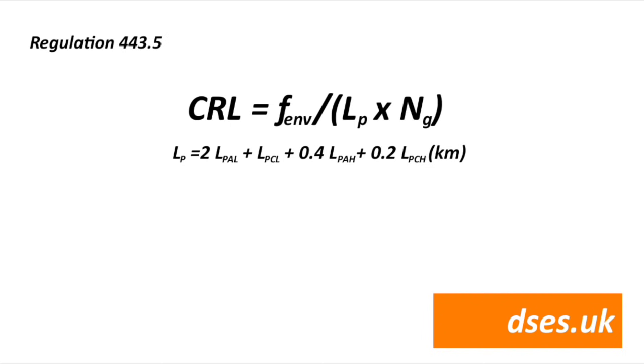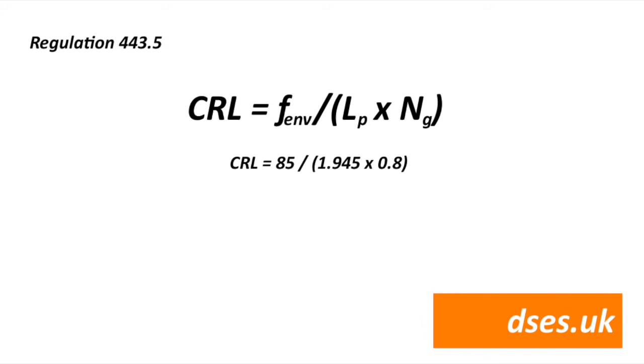As I only have numbers for LPAL and LPCL, I'm disregarding LPAH and LPCH. That's what they seem to do in a few worked examples in the blue book. Anyway, as the formula works in kilometres and we have values in metres, we'll shuffle the decimal points around. So take 0.945, multiply by 2 and add to 0.055, which gives us 1.945 as a value for LP. Okay, let's plumb all that into our original formula for the calculated risk assessment. 85 divided by the product of 1.945 multiplied by 0.8, will it be higher or lower than 1000?